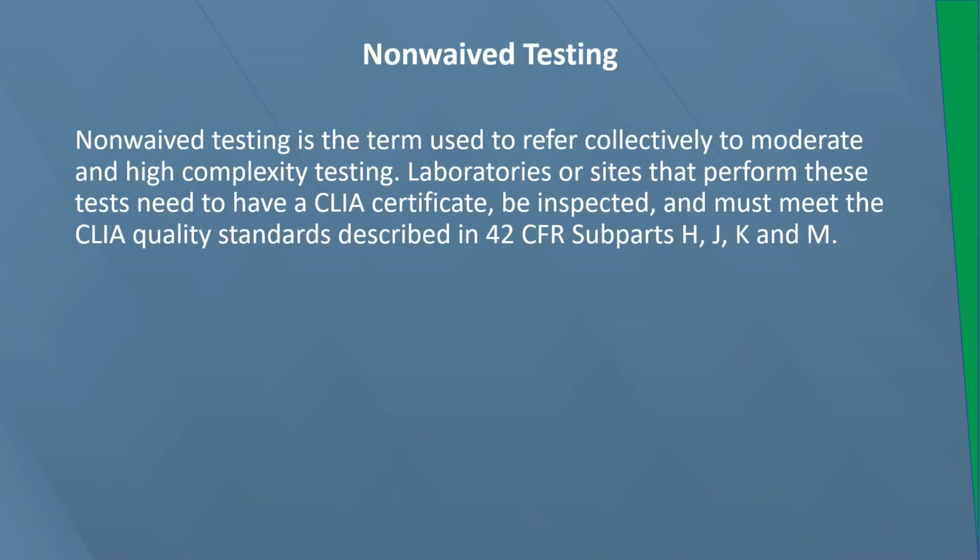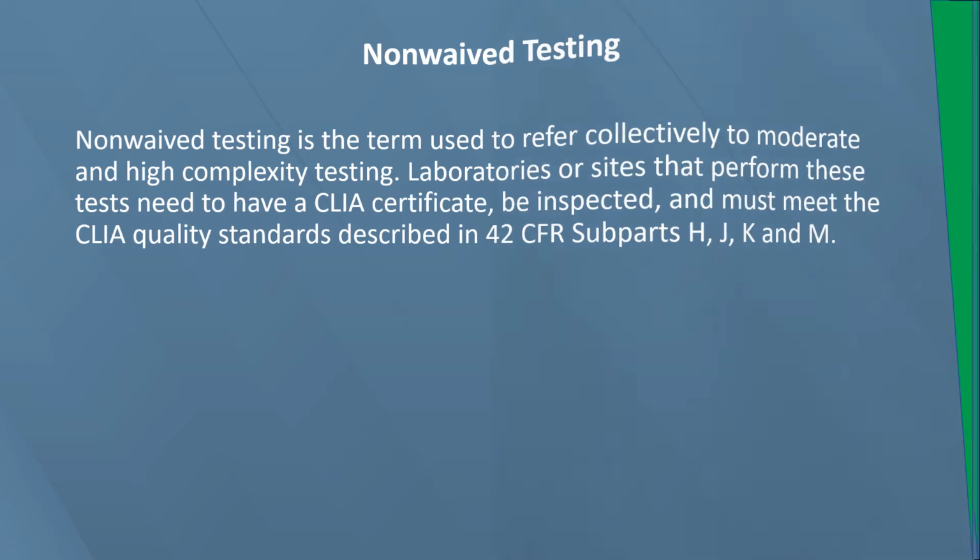Non-waived testing. Non-waived testing is the term used to refer collectively to moderate and high complexity testing. Laboratories or sites that perform these tests need to have a CLIA certificate, be inspected, and must meet the CLIA quality standards described in Title 42 Code of Federal Regulations subparts H, J, K, and M.